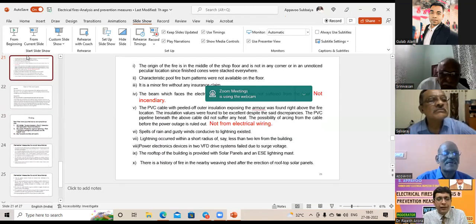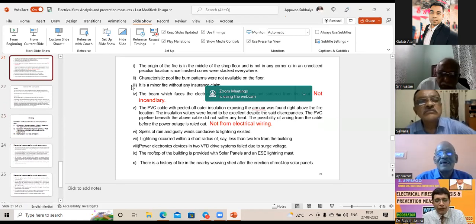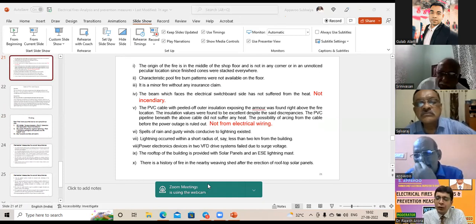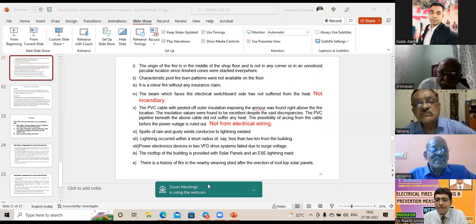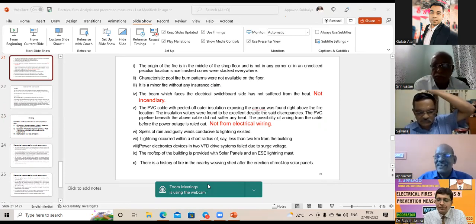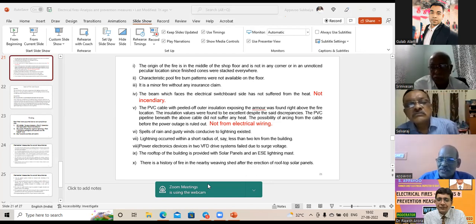Sir, with your due permission, I want to ask one question related to slide number 21. In slide number 21, you have mentioned there was failure of VFD drive due to surge voltage. I just want to understand, was there provision of any SPD or not? If an SPD was there, was it working or not? Yes. I suggested in my recommendation, and I went through it faster because of the time restriction, that the SPD was not there. I recommended providing SPD. Okay. No surge protection device right from the beginning up to the final end. Even the lightning protection was non-standard. There is no SPD within the LT panel for the transformers also.